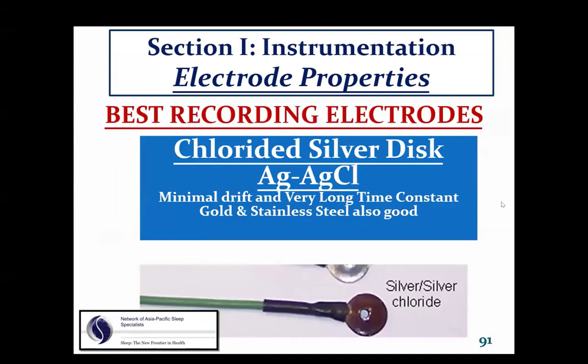The best recording electrode is chlorided silver disc electrodes, and that's AgCl. Now, for a long time, and you might find in some of your older labs, everyone says the best electrode is gold. And that used to be true, because gold electrodes were made out of pure gold. Now, because of the cost of gold, they are gold coated, which really makes them a lesser choice compared to silver chlorided electrodes.